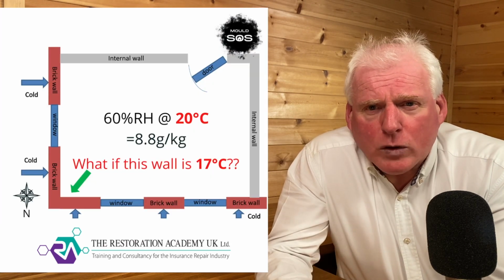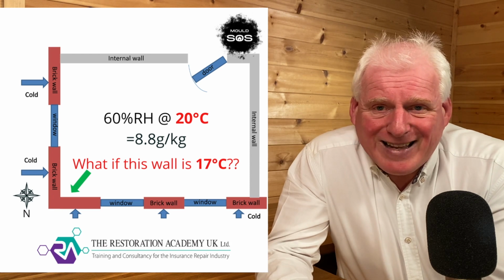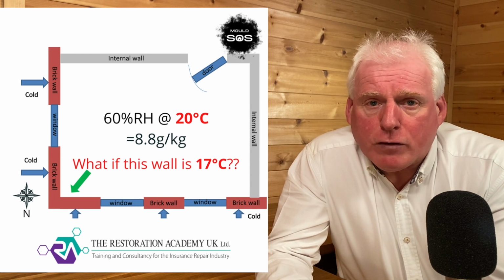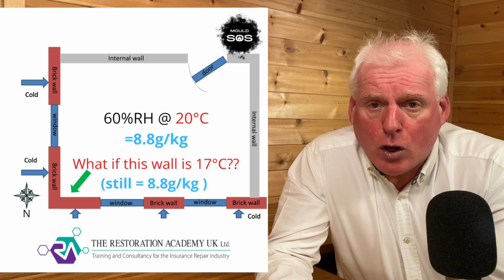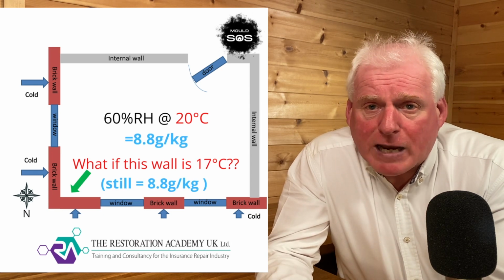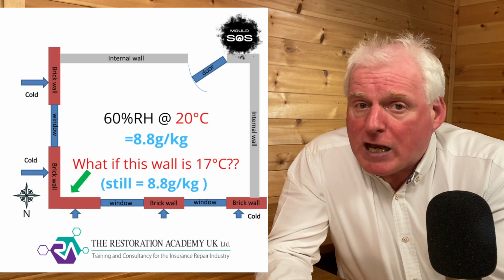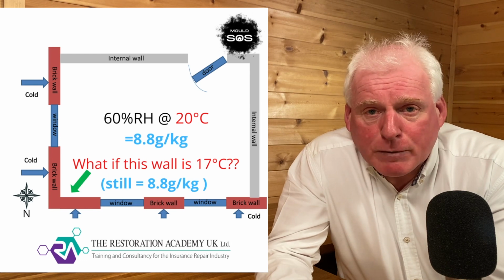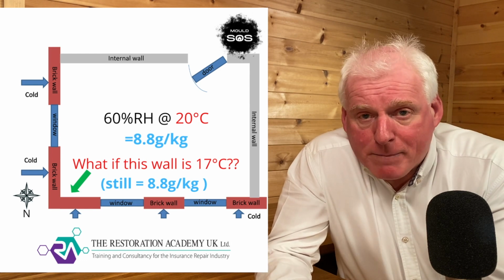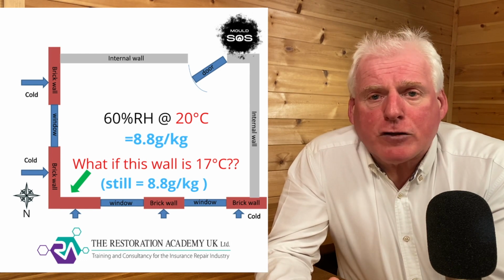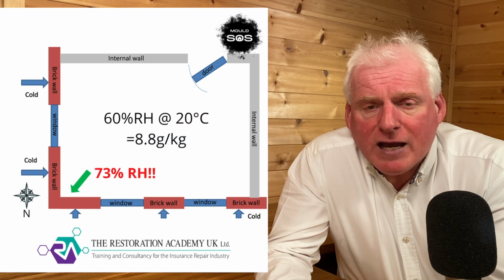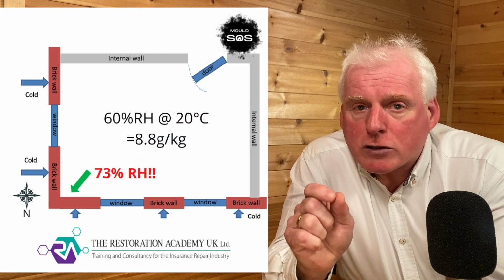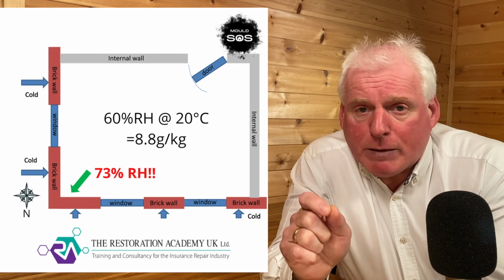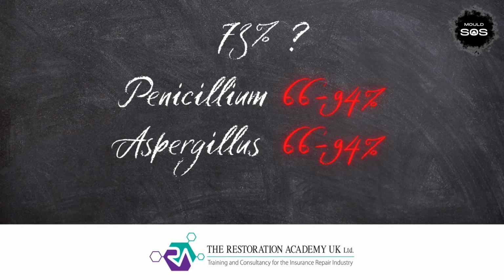But what happens if the wall is cold in a particular spot? Let's say the surface temperature of that area of concern of the wall is 17 centigrade. Well, if we know the amount of water in the air is 8.8 grams per kilogram in the middle of the room, it'll be the same at the wall, because that has to be true across the whole room. Remember, equilibrium. If the temperature of the wall is 17 centigrade, then the sliver of air closest to the wall surface is 73% RH. That is a number high enough for some moulds to germinate and grow.